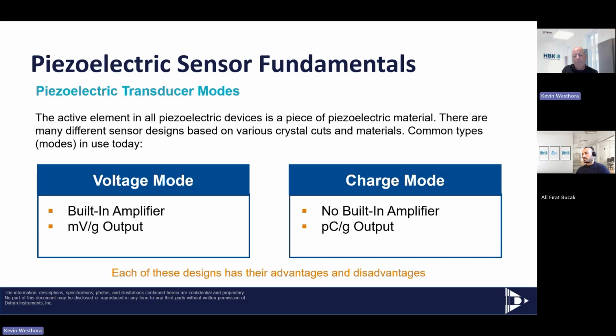In my opinion, you would never use a charge mode accelerometer except for one reason: the temperature limitation of the amplifier in the voltage mode accelerometer. The voltage mode amplifier is limited to roughly around 160 C. Once you get above that, we need to take the amplifier out of the accelerometer and put it somewhere else. The amplifier has a name, but the accelerometer industry is a very strange industry, in my opinion.